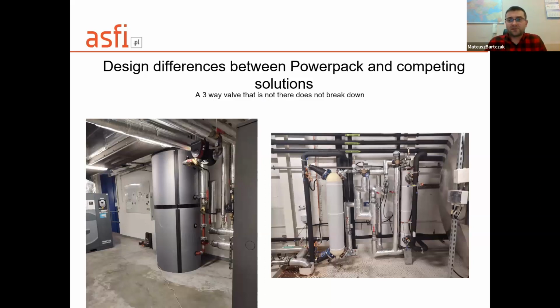One more danger is connected with this valve. I wrote several publications on LinkedIn about them getting stuck. A constantly operating valve wears out; the question is not if, but when it will get stuck. In this implementation, the valve was stuck on the exchanger bypass. What does this mean? If it were not for our automation and measuring system, the customer would think that he recovers heat, but they can recover nothing because the oil is bypassing the exchanger. Only a valve which does not exist cannot get stuck.